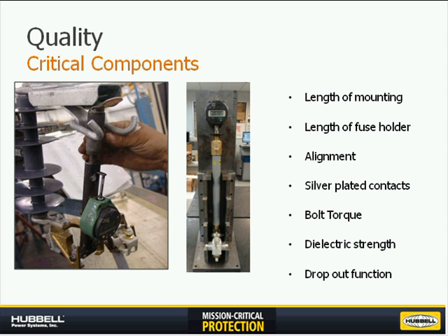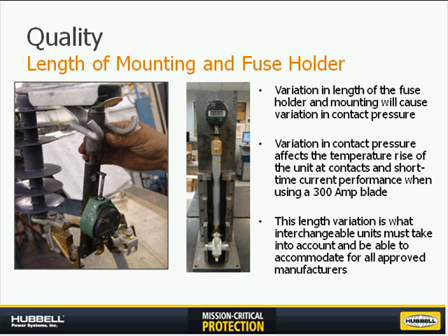The first two critical components we're going to discuss are the length of the mounting and the fuse holder. As you can see in the leftmost photo, this is a gauge tool used to check what we call the gauge length of the mounting — the distance from your rotation point in the hinge (your bottom brass or bottom aluminum bronze component) to the silver plated top contact. This is where the standard interchangeable fuse holder engages. Maintaining this length is what allows you to perform in momentary testing with a 300 amp blade, and gives you your contact pressure to maintain low temperature rise during 300, 200, or 100 amp continuous current operation.